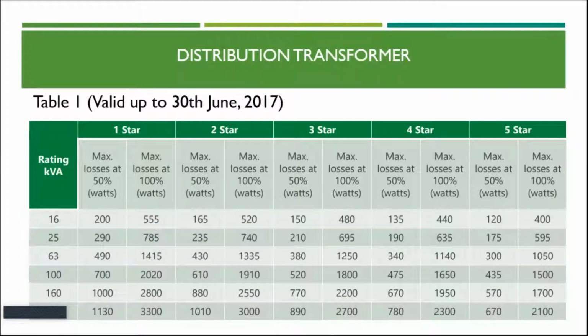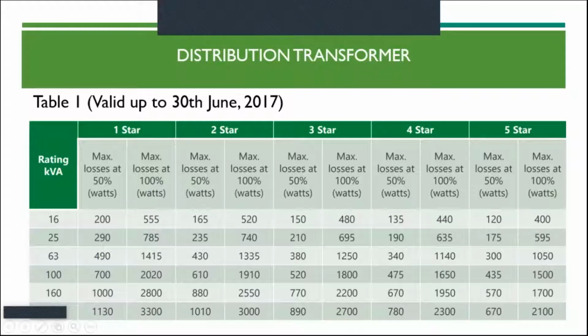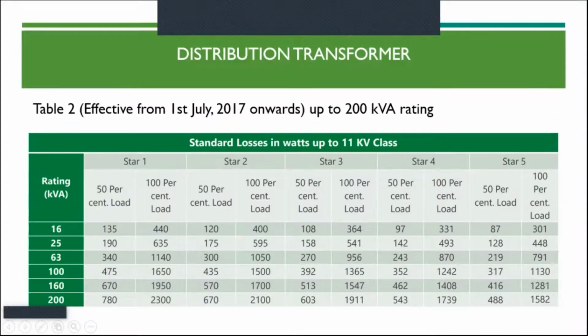Distribution transformers are also being rated from 1-star to 5-star. They are rated by taking the maximum losses at 50% loading and maximum losses at 100% loading. This was valid up to 2017. Now it has been revised again. In 2017, 4-star rated appliances were made mandatory. Distribution transformers were made mandatory in the state of Punjab, where for the 16 kVA the losses were 135 at 50% loading and 440 at 100% loading. This has now been revised as star 1.